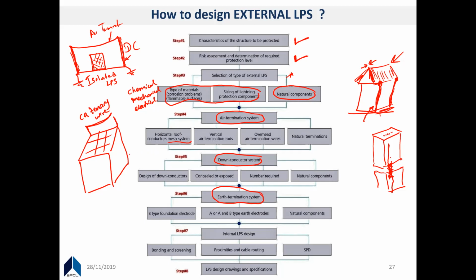Immediately after going through these concepts of evaluation, I will do a small design with these air terminations. And you can have these vertical air termination rods and overhead air termination wires, and also natural terminations, right? So if you have a steel roof, you have to make sure of the thickness. If you do not consider the thickness, then you have to absorb the risk. If it says it shall be like 6 millimeter thick, you have to make sure of that, or the standard itself says that otherwise it will cause punctures. Punctures means during a lightning flash, there's a risk of puncturing of the roof.